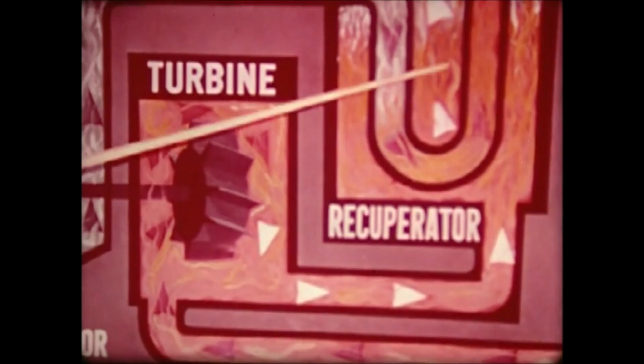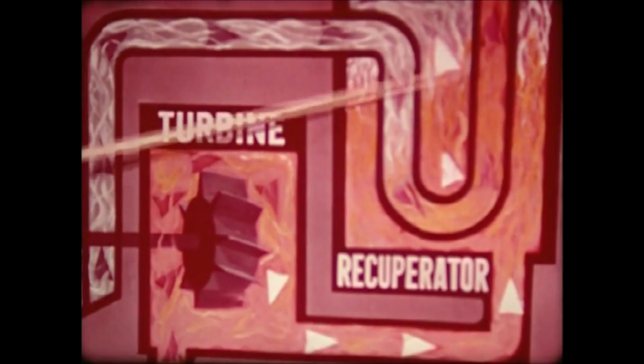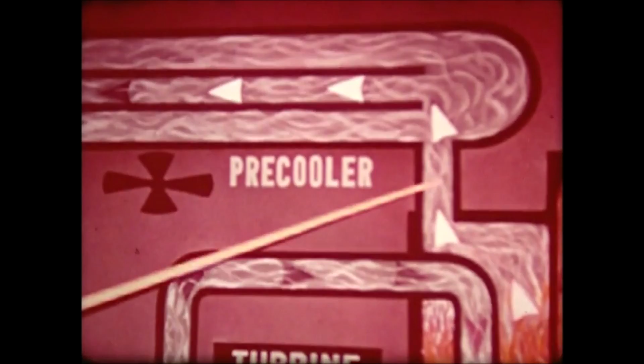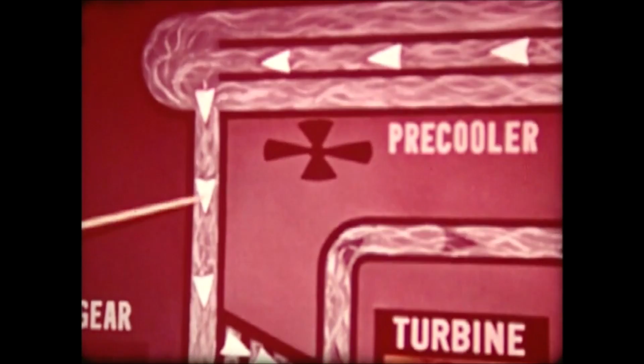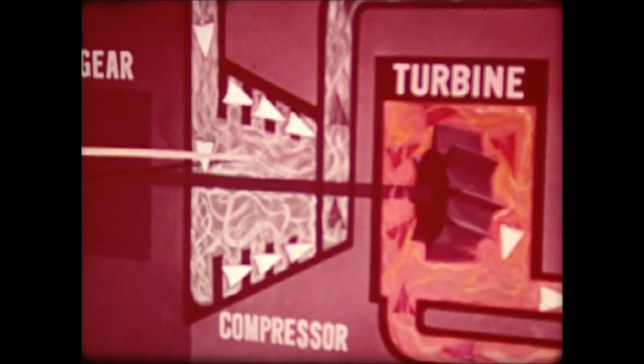After leaving the turbine, the gas, which is still extremely hot, passes to a recuperator. This recuperator does a remarkable job of transferring several hundred degrees of this excess heat to a cooler gas in approximately 0.08 of a second. The gas is cooled even more in a pre-cooler. This additional cooling lowers the gas temperature prior to entering the compressor section of the turbine compressor set.